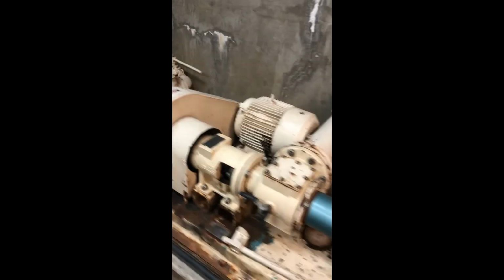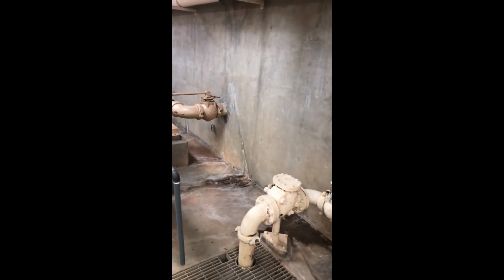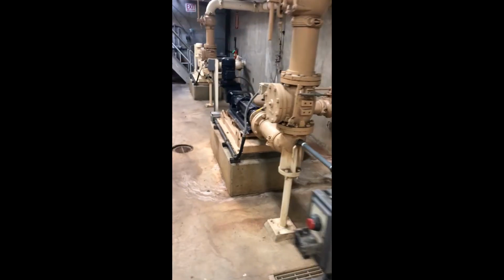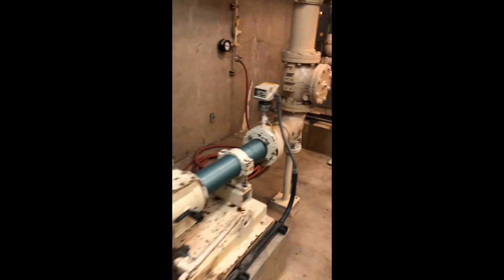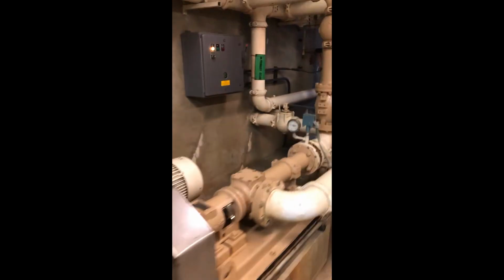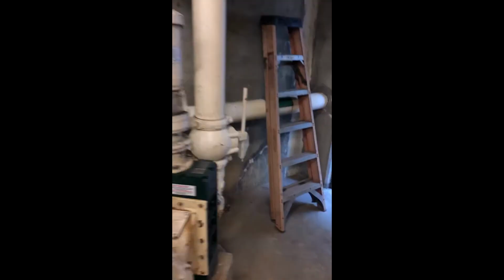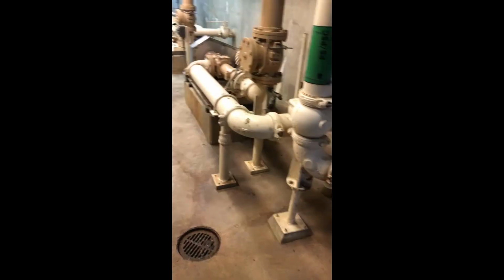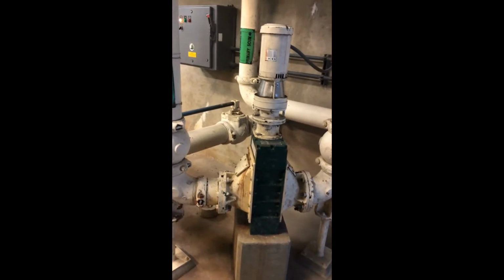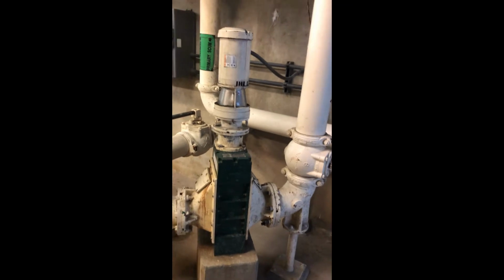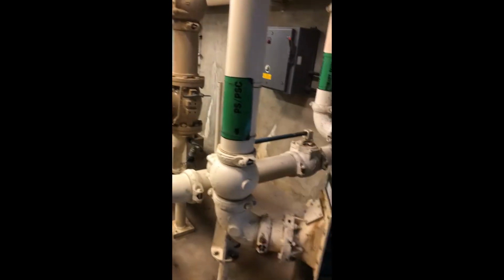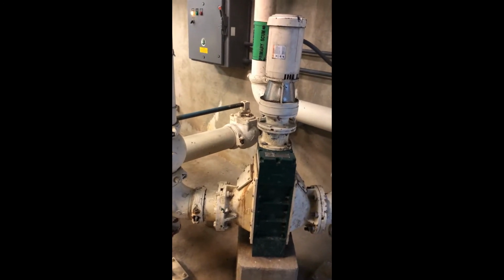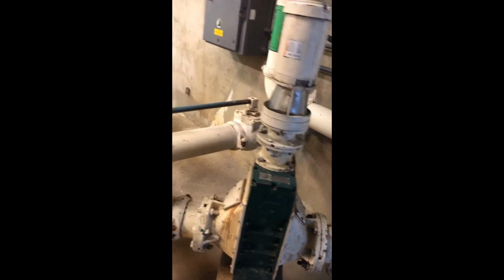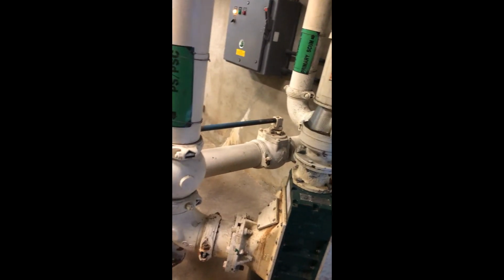These are the primary sludge pumps here. On the other side of this wall is that sump I was talking about where all the heavy stuff falls to. And these are the pumps that come on periodically to take all that sludge, that thick stuff that's settled to the bottom of the tank, and of course sends it over to the digester. These are typical, this particular machine. This is called a grinder. It takes the primary sludge and it sends it through this grinder before it sends it through the pump. It's better for the pump, if something gets through that's kind of large and not good for the pump, then this grinder will chop it up first.